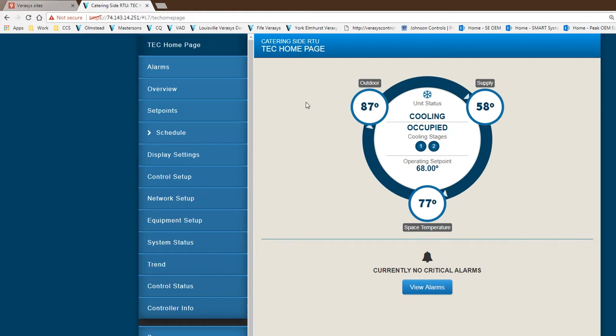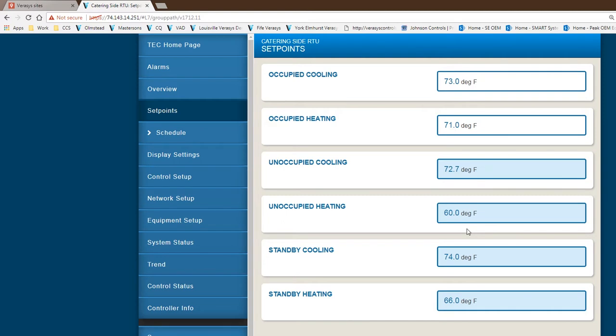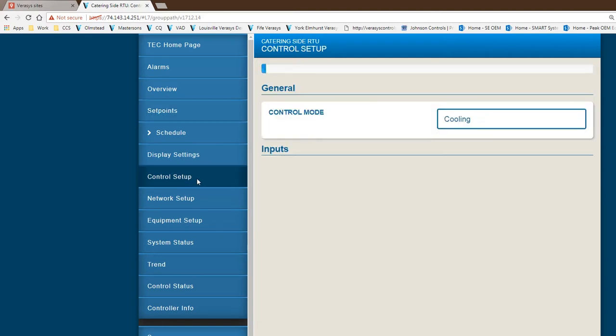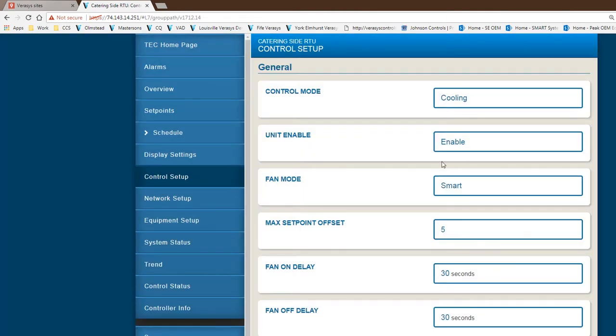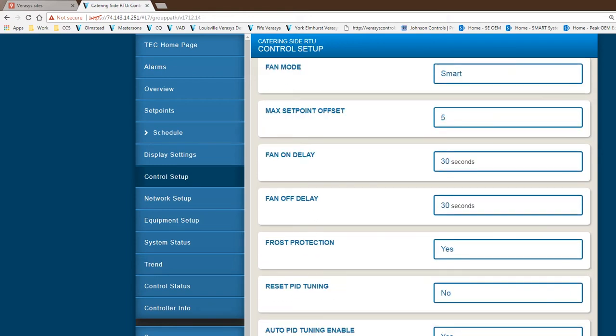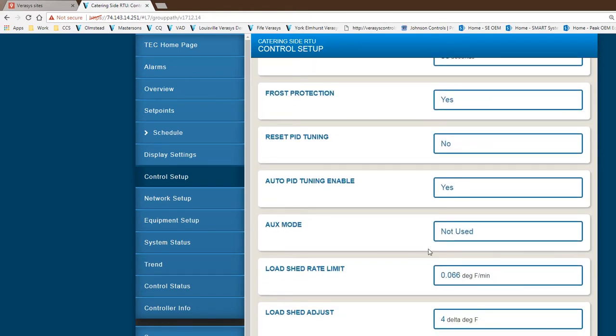This particular equipment is controlled by what's called the TEC, and the TEC set points are changed in this page. You'll see different menus you can go into for this controller. If I need to change the control setup, I could go here and make necessary changes. For example, if I want to change the control mode from cooling to auto, so it switches from cooling or heating. In this case, the customer decided to keep it in cooling. A lot of different configuration can be done, just questions, answers, yes or no, not used, or different parameters you put in.